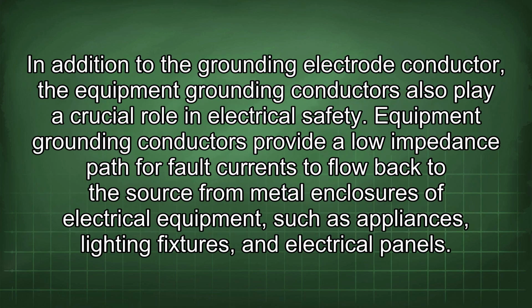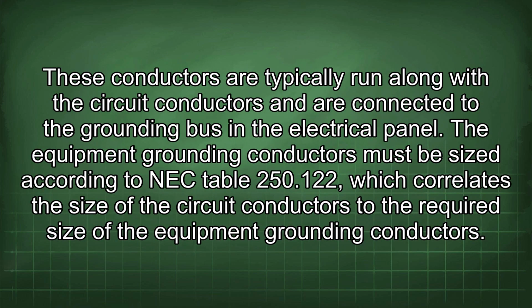In addition to the grounding electrode conductor, the equipment grounding conductors also play a crucial role in electrical safety. Equipment grounding conductors provide a low impedance path for fault currents to flow back to the source from metal enclosures of electrical equipment, such as appliances, lighting fixtures, and electrical panels. These conductors are typically run along with the circuit conductors and are connected to the grounding bus in the electrical panel. The equipment grounding conductors must be sized according to NEC Table 250.122, which correlates the size of the circuit conductors to the required size of the equipment grounding conductors.